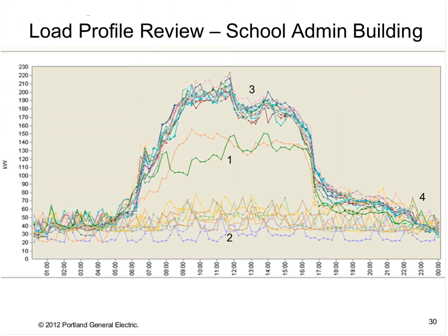This next example is another school building, and I've numbered these 1 to 4, and I'll start with number 1. Number 1 is actually a weekend day, but you're kind of wondering, okay, why are there 2 days there? This is actually Thanksgiving weekend. I'm not sure what happened or why anything was on this weekend. They could have had a community Thanksgiving, but me not knowing the building schedule, I don't know that. So I would think either something was left on, HVAC was going on.